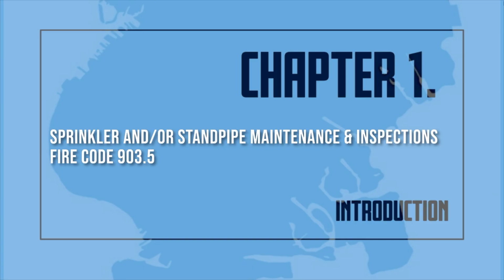2. A supply of at least 6 extra sprinkler heads shall be kept available on the premises to replace promptly any fused or damaged sprinklers. Any head which has opened or has been damaged shall be replaced immediately with a sprinkler head of similar characteristics such as operating temperature, orifice size, deflector orientation, and thermal sensitivity.